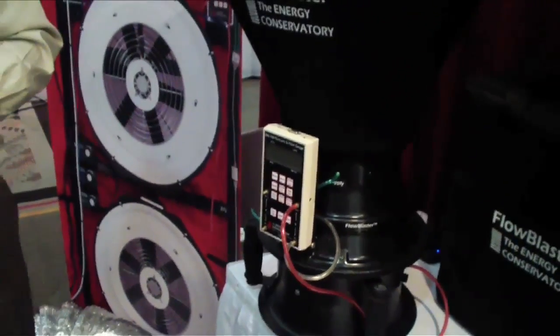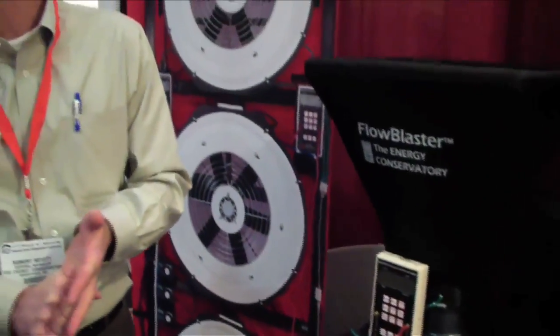It's designed to measure both return and supply air flows from 10 CFM to 300 CFM range. It doesn't go above 300 at the moment, but for most residential and certainly in passive houses, that's just fine. That's all you need in a passive house.